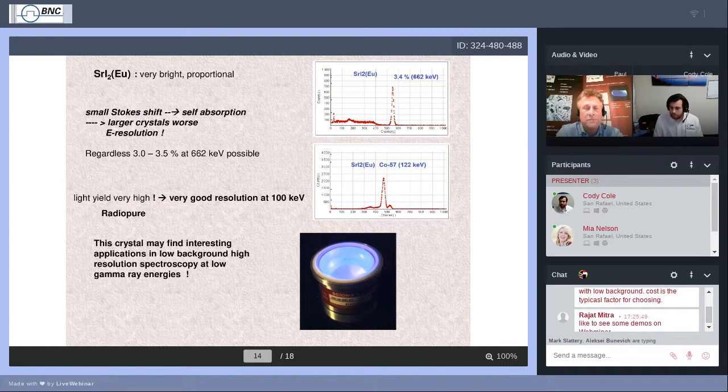Okay, and would that lend information to why the cobalt-57 peak channel seems to be very close to the Cs-137 peak? No, the calibration is different. Those spectra don't have the same calibration. It's not a calibration in keV. It's an arbitrary channel. The two peaks in the spectrum at the bottom are 122 and 136.